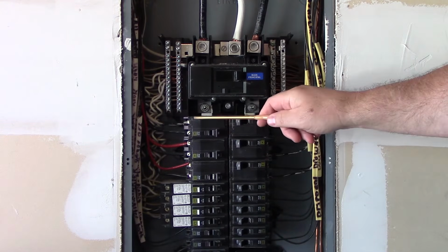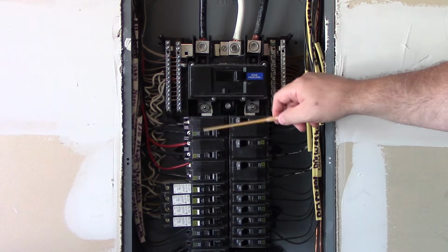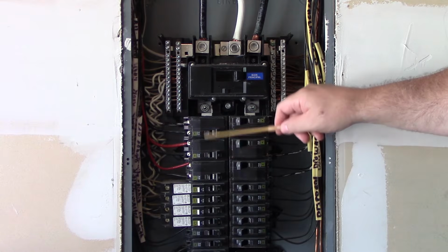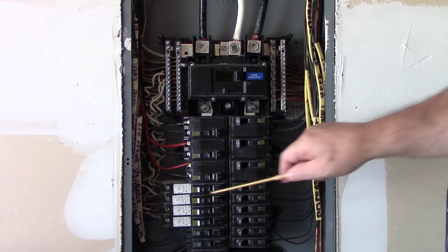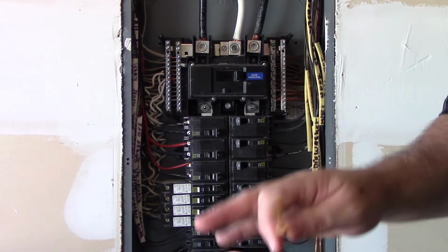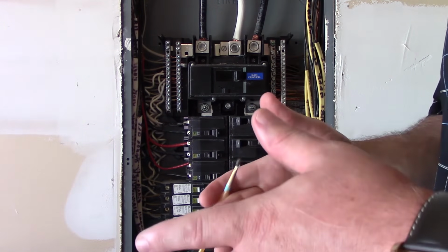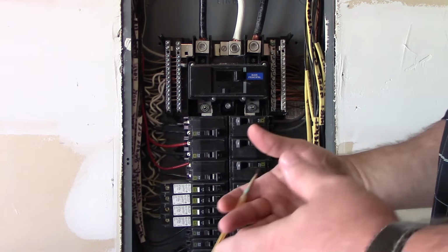Okay, so that's why you want to make sure it's two pole breakers with an identified handle tie, or two single pole breakers, identified handle tie. You want to make sure they're installed properly in the enclosure and not spread out and accidentally on the same leg, because that could be a problem. The current becomes cumulative at that point, and you will overload a neutral.